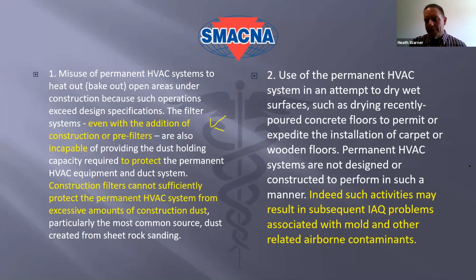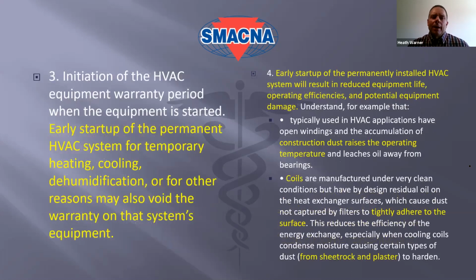There are all kinds of studies, if you start looking into it, of systems that have been used to dry out floors so they can put gym floors down, VCT tile down, a myriad of studies out there that will show you that it exponentially increases the chances of mold growth within the ductwork. Early startup of the permanent system for cooling and dehumidification is going to void your warranty. Most of the time an HVAC contractor is not going to tell you that, or they're just being told to go ahead and bring it online. Generally, the owner has not been told that.